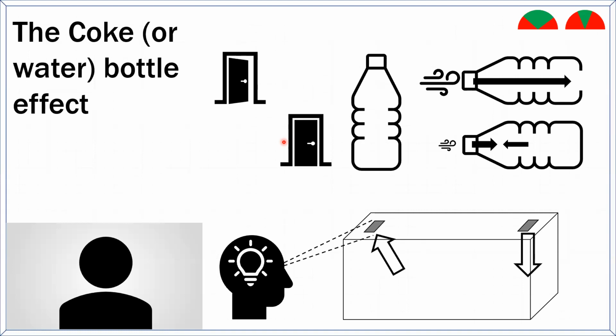It put a negative pressure on the home and sucked in air in all kinds of other places. But it was nighttime and the load wasn't crazy high, and we had low sensible heat ratio equipment, so people didn't really notice. They woke up in the morning and went downstairs. It was a little more humid than they were used to, but we got air into our bedrooms.